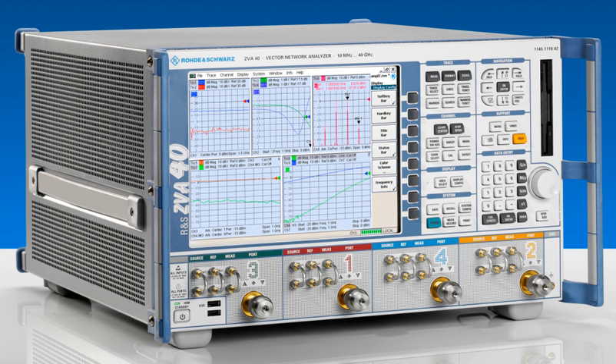A modern network analyzer will have data stored about the devices in a calibration kit, Keysight Technologies 2006, for the open circuit. This will be some electrical delay, typically tens of picoseconds, and fringing capacitance which will be frequency dependent. The capacitance is normally specified in terms of a polynomial, with the coefficients specific to each standard. A short will have some delay, and a frequency-dependent inductance, although the inductance is normally considered insignificant below about 6 GHz.